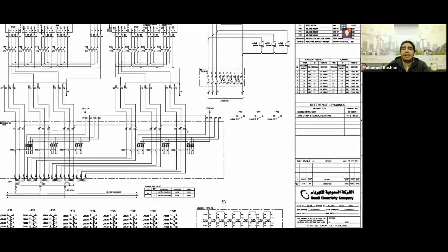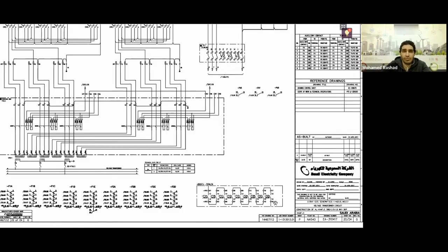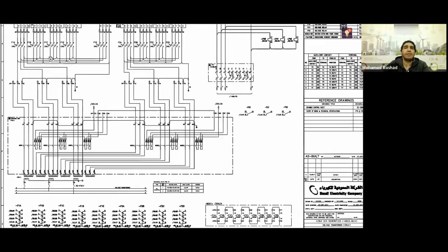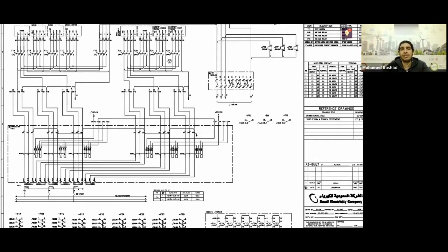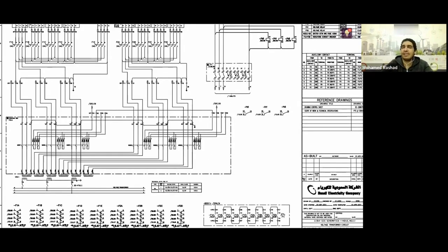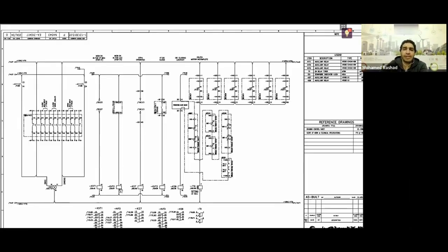Of course, all of these here are auxiliary contacts, normally open contacts from the set of miniature circuit breakers present in the LCC, which you must ensure are all closed. Naturally, the normally open contacts are set so that when the MCB closes, all these contacts will close. So when all these contacts close, KVT2 will also operate.